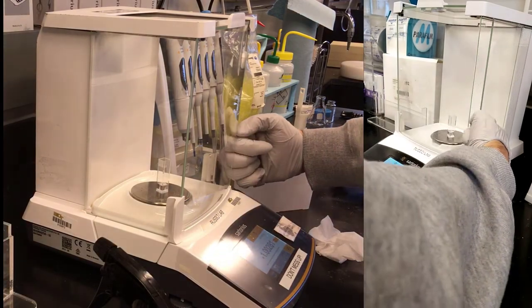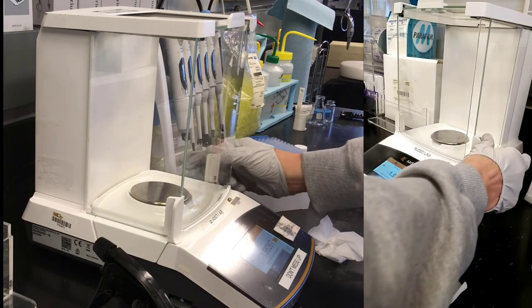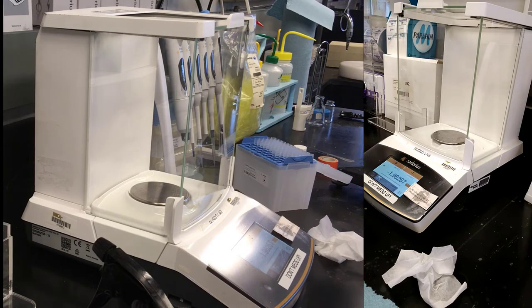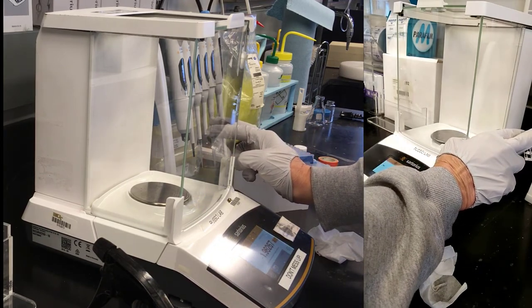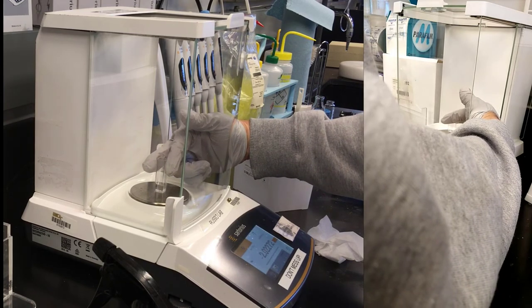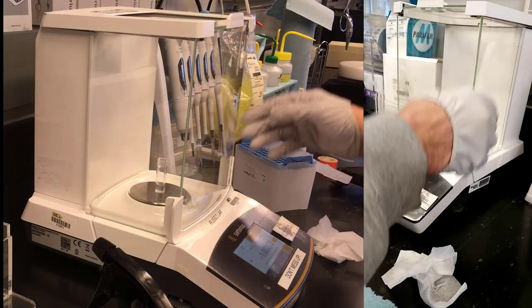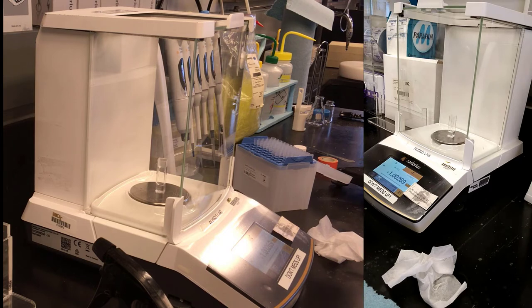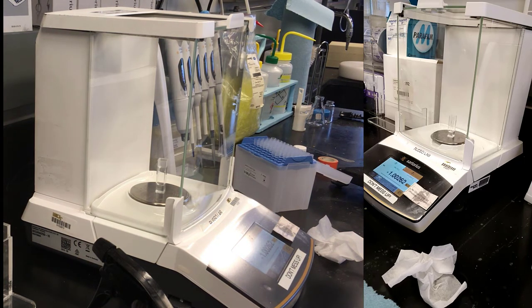Well, you might be interested to know just how reliable that is, 1.00281. So you can just remove that. Notice that we're always very gentle with these doors. They're made of real glass. They will shatter. It would be expensive to fix them. And what's worse, you'd have to go through GT procurement to fix them. So that's not going to be fun. Let's put it back. Notice that now it reads negative because I had tared it. And if I hadn't written down the amount of the actual cell before I tared it, I could be in trouble with this. Sometimes you really want to know the empty weight. So I always write the tare weight down. Let's give it a chance to come back.